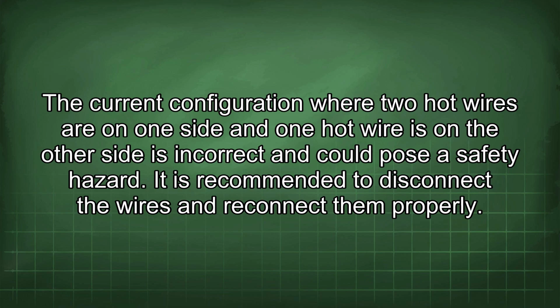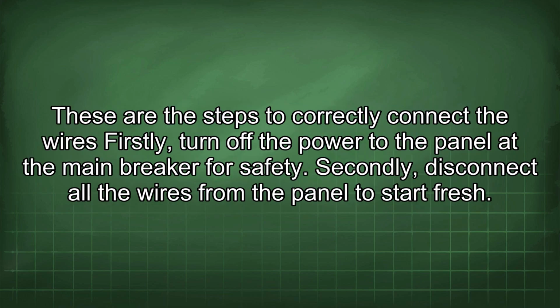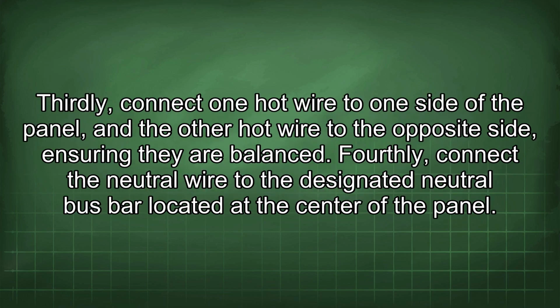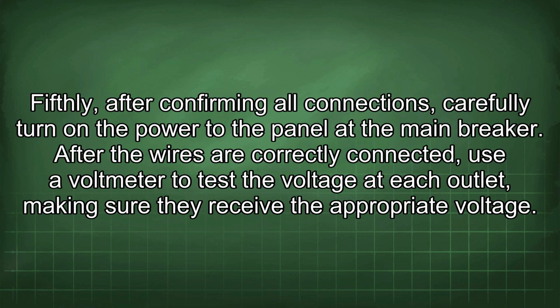It is recommended to disconnect the wires and reconnect them properly. These are the steps to correctly connect the wires. Firstly, turn off the power to the panel at the main breaker for safety. Secondly, disconnect all the wires from the panel to start fresh. Thirdly, connect one hot wire to one side of the panel and the other hot wire to the opposite side, ensuring they are balanced. Fourthly, connect the neutral wire to the designated neutral busbar located at the center of the panel. Fifthly, after confirming all connections, carefully turn on the power to the panel at the main breaker.